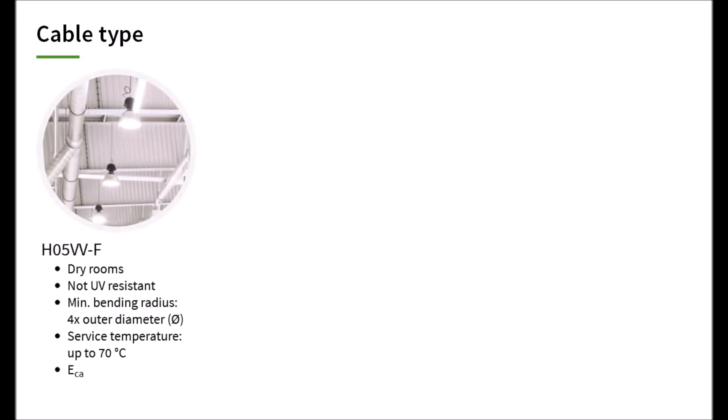The selection of the suitable cable is of utmost importance for a safe and long-lasting operation of the installation. We offer the low-priced H05VVF cable as standard, but its field of application is limited to indoor use. This cable is not suitable for outdoor use and permanently damp or wet rooms.